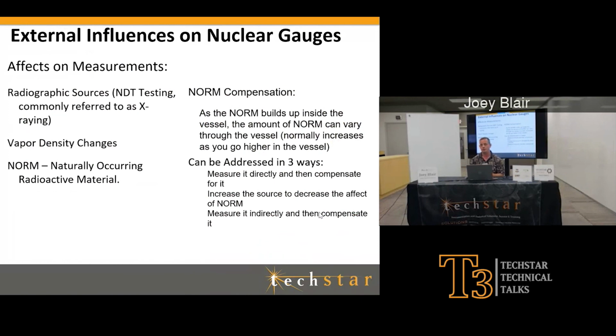Let's say my vessel's completely empty. I'll give you a couple scenarios. Let's say we're in turnaround - we've had this detector on here for a while, and they have just come down, right? They assumed everything was right. They've been trusting this gauge for years, and they trust it. Now they come down, and it stops coming down at 15%, and it doesn't get any lower than that. I'm like, well heck, this thing's been inaccurate all along, it's 15% off. Not necessarily, okay? It was calibrated - remember, it was calibrated to process conditions. So just because it's reading 15% and you went down, what could be happening right now?